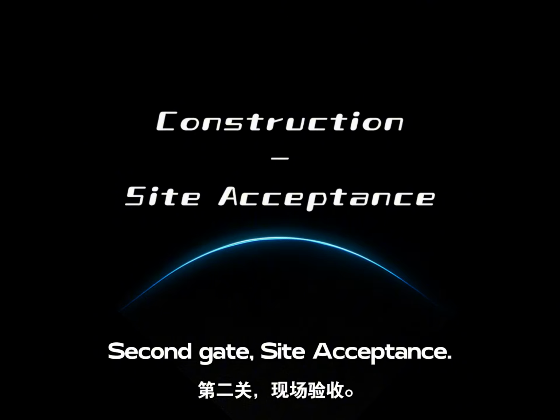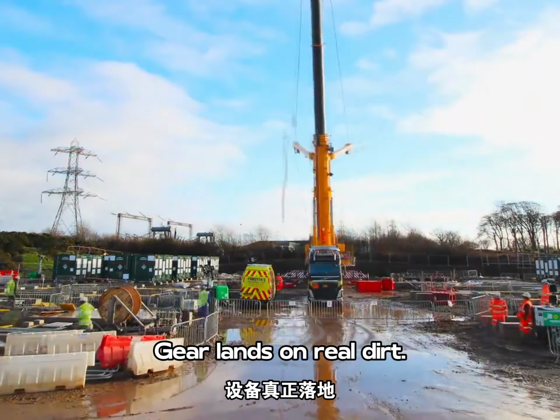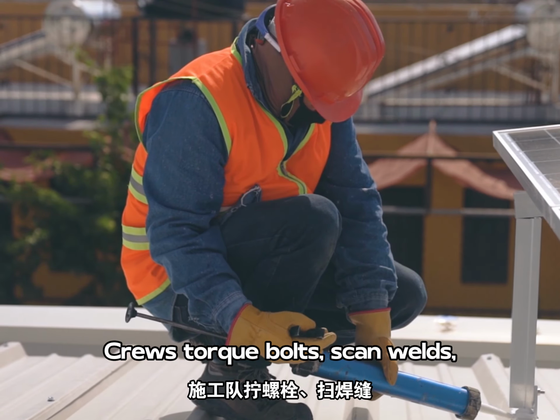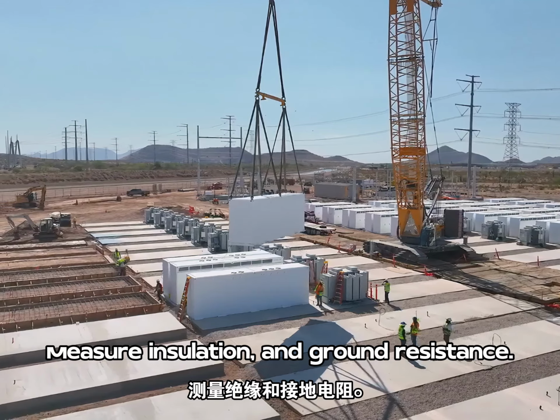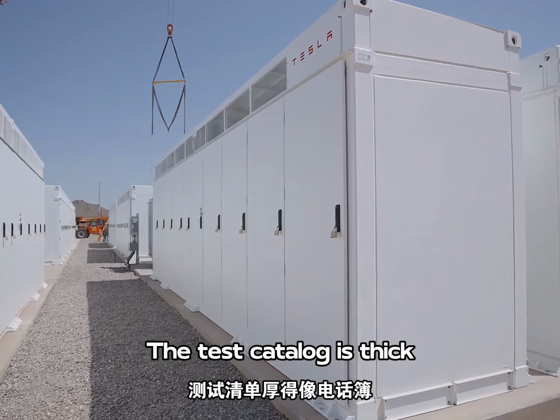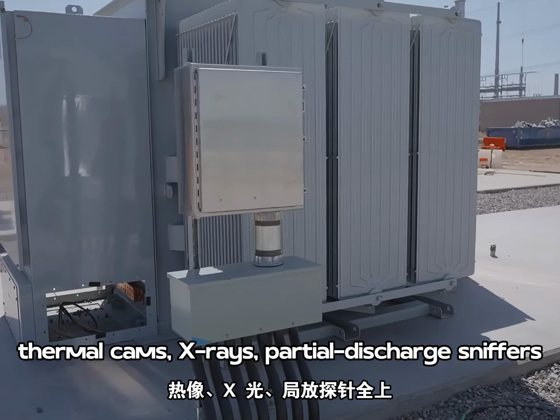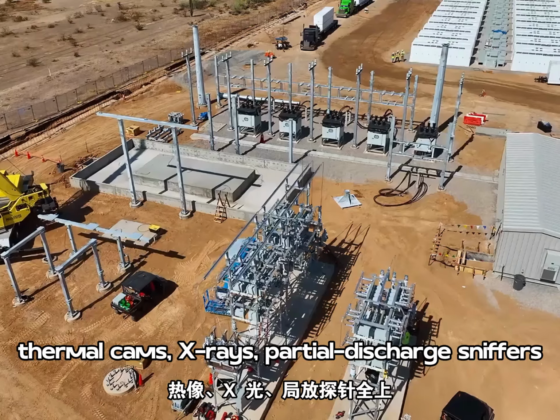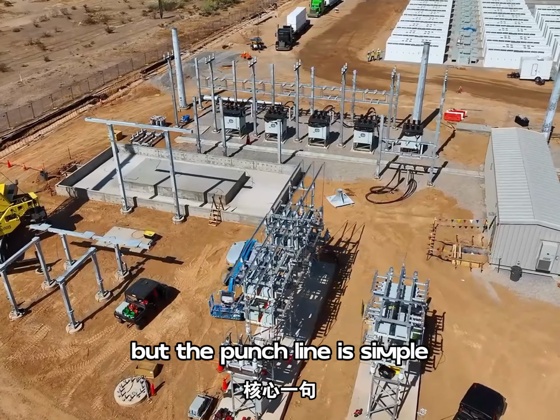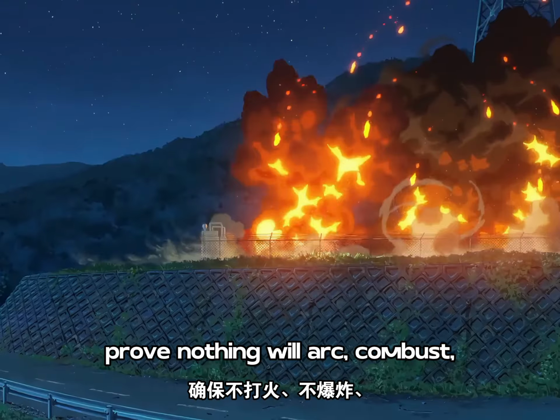The second gate is site acceptance: the gear lands on real dirt. Crews torque bolts, scan welds, measure insulation and ground resistance. The test catalog includes thermal cams, X-rays, and partial discharge sniffers, but the punch line is simple: prove nothing will arc, combust, or electrocute the neighbor's cow.